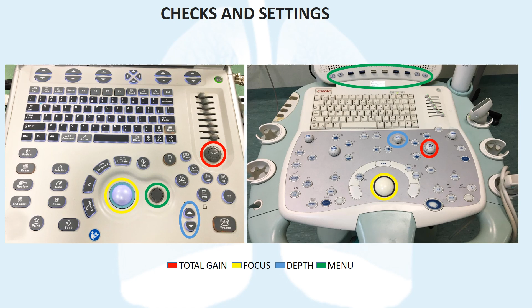In red, we have identified the gain button that allows us to increase or reduce the intensity, also called gain. The button that allows us to regulate the depth is identified in light blue, while in yellow and in green we can respectively identify the trackball and the buttons for the main menu's ultrasound settings. When performing a pulmonary ultrasound, it is necessary to set the focus on the pleural line and to regulate the depth of the image. One thing to keep in mind is that pulmonary ultrasound is an imaging method that receives a lot of information from the artifacts rather than from direct, clear images.